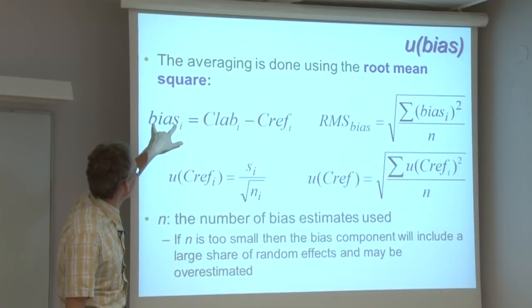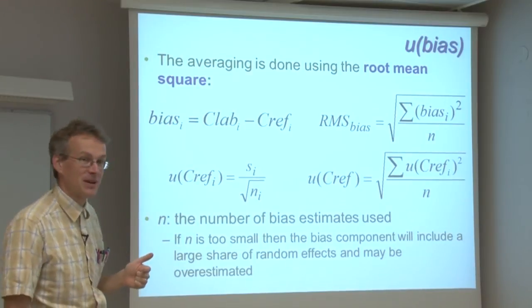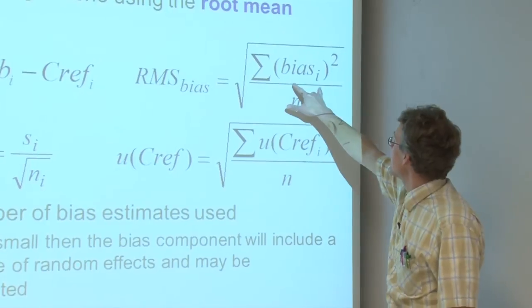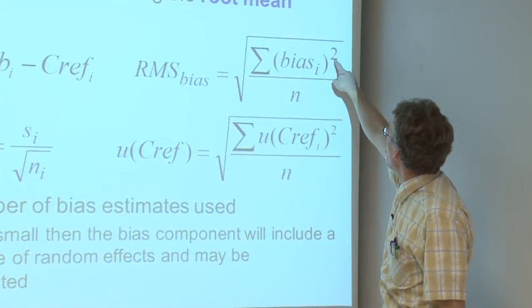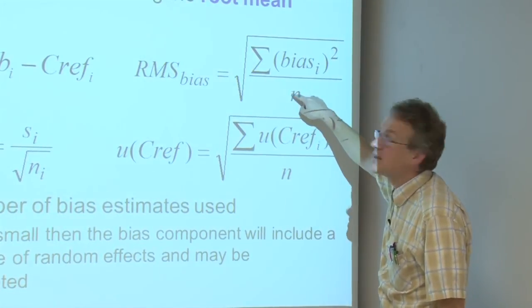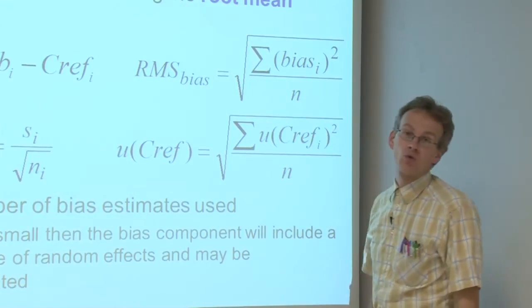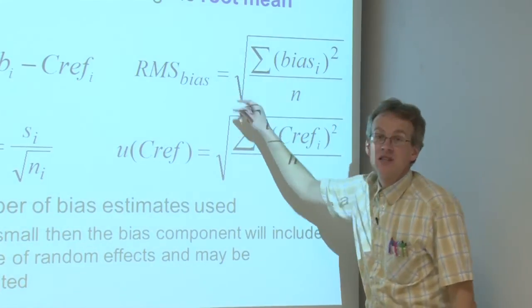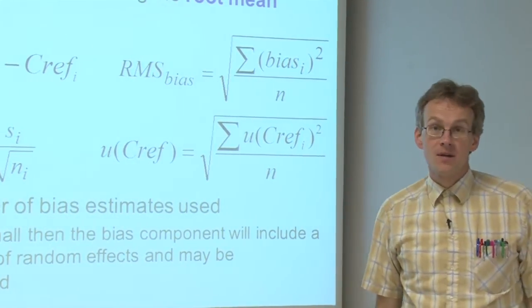You should obtain several bias values, preferably from several different reference materials or interlaboratory comparisons. The RMS_bias is then found as follows: you take all your bias estimates, square each of them, sum all the squares, divide by the number of bias estimates, and finally take the square root. This averaging procedure is called the root mean square approach, which is where the RMS comes from.